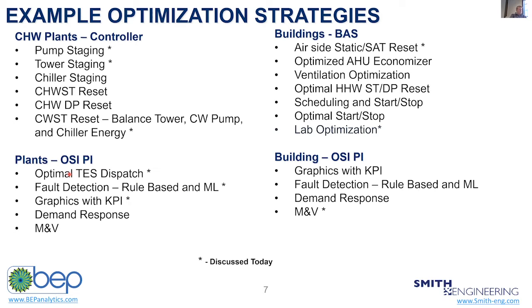Some examples of things that should be done in an analytics platform are TES dispatch. Thermal storage dispatch gets very complex and is too complicated for the controller to be done properly. Obviously, the thermal storage control can be done within the controller, but when to charge and when to discharge, when to run a steam turbine chiller, when to maximize the output of the gas turbine, when to minimize the output of the gas turbine. These are things that require a load prediction to be done optimally, and a good load prediction requires complex analytics. Some other examples: demand response, measurement and verification. To do that right on a real-time basis needs an analytics platform.